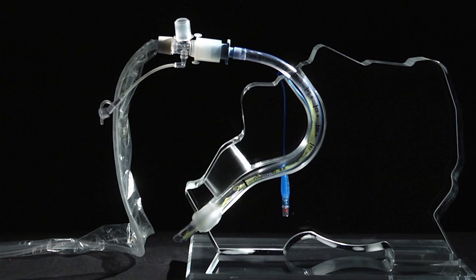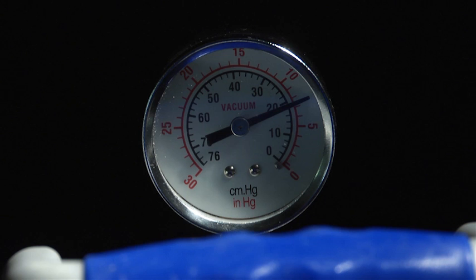What you see is an anatomically correct acrylic see-through human head, and into that is inserted a standard 8mm endotracheal tube and connected to a standard closed suction system. The suction that you hear in the background is at 180 millimeters of mercury, which is on the high side but clearly within the limits for closed suction.